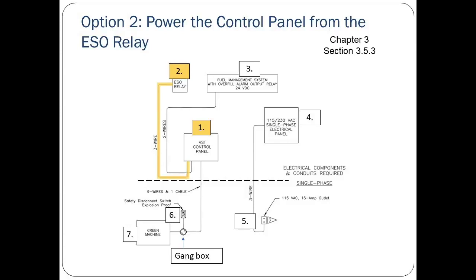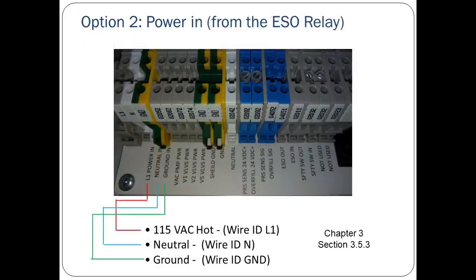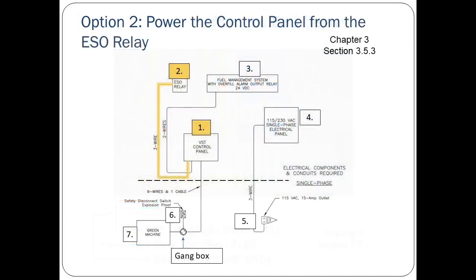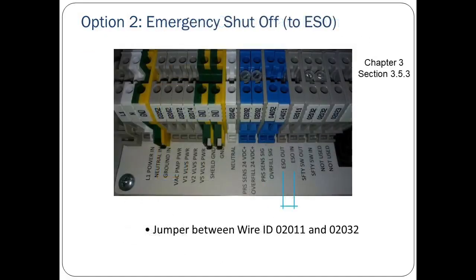For Option 2, we'll be powering the VST control panel directly from the ESO relay. Just like in Option 1, the power wires must be terminated at these locations inside the VST control panel. Recall that in Option 1, the VST control panel needed to be wired to the station ESO so that the control panel and green machine lose power if the ESO system is activated. In Option 2, the VST control panel is powered directly from the ESO. Because of this, a second connection to the ESO is not needed. While the second connection to the ESO is not needed, current still needs to flow between these 2 terminal blocks. Simply install a jumper between these terminal blocks to complete Option 2 of powering the control panel.